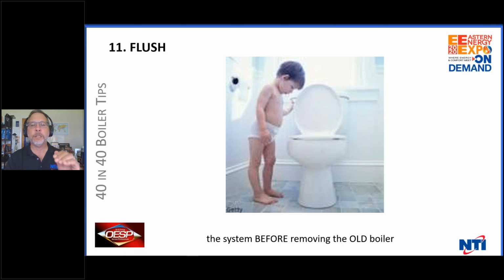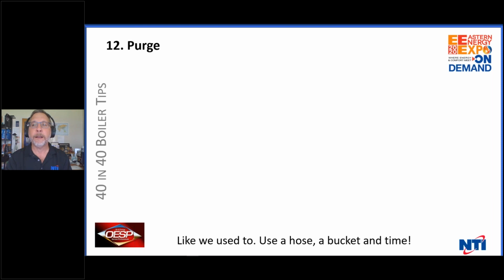It will kill tube sheets. It will crack sections. It will destroy condensing boilers. The smaller the heat exchanger, the worse it's going to affect the boiler. Please, for God's sake, flush this system before you take the old boiler out. And of course, make sure you put down tarps so when you take it out, you're not putting that black stuff all over the floor.